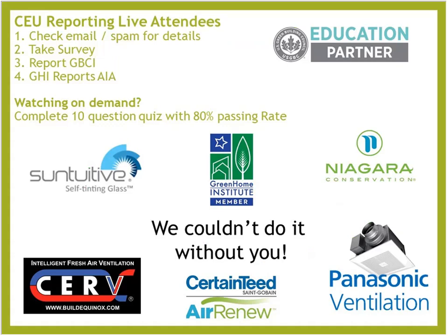So recirculation, the value of that in a smart ventilation system is that we are sensing the return air, so the bulk combined, and keeping the whole house as uniformly as we can at a lower level of CO2 and VOCs. And what this amounts to on a practical basis in most homes is that about 20% of the time we'll be in fresh air ventilation at about 150 to 200 cubic feet per minute.